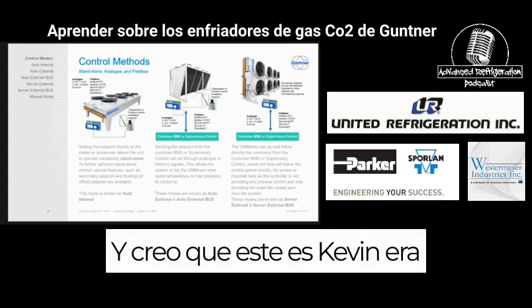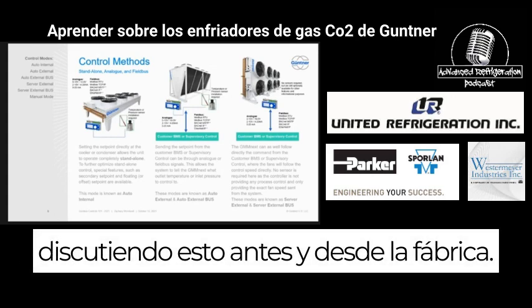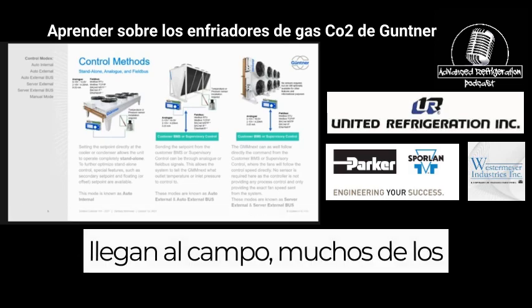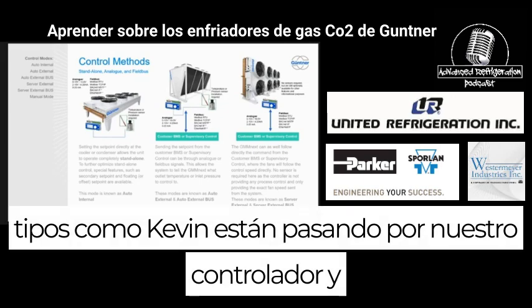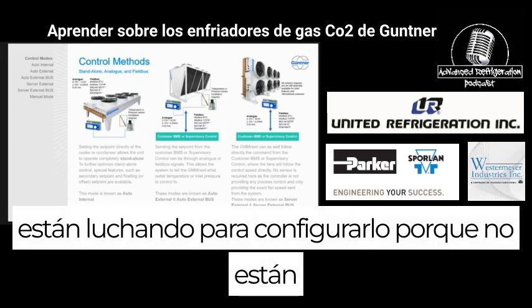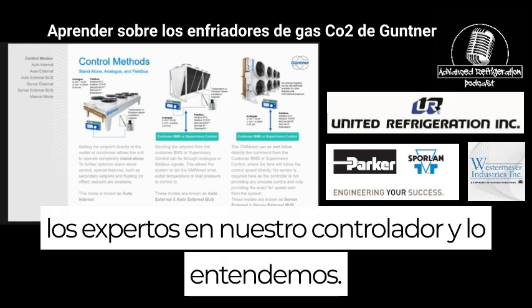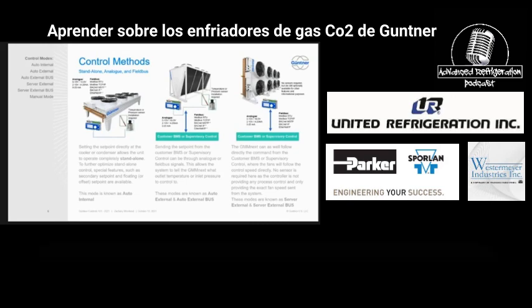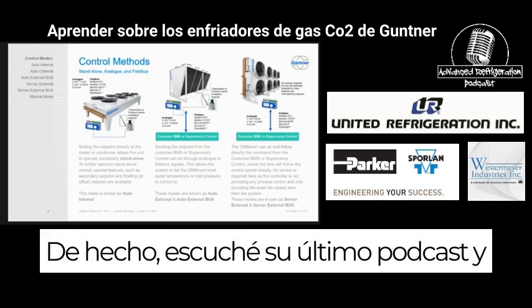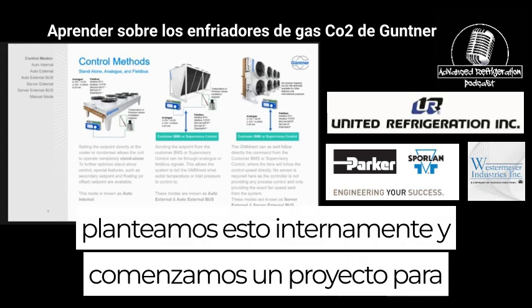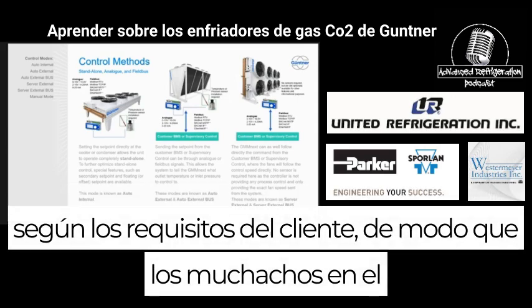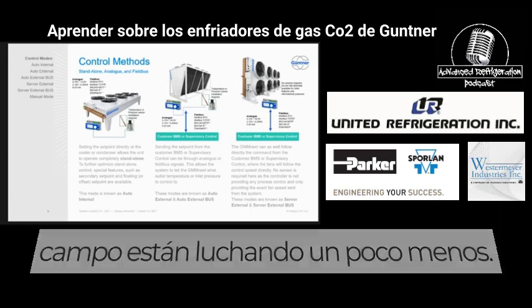Mm-hmm. Kevin was discussing this before: from the factory, our units usually come in standalone mode. So when they get to the field, a lot of guys like Kevin go through our controller and struggle to set it up, because they're not the experts in our controller and we understand it. They could fumble through it, it's not working, and it could get very frustrating. I listened to your last podcast and brought this up internally, and we started a project to make sure our controllers leave the factory set up per customer requirements, so the guys in the field struggle a little bit less.